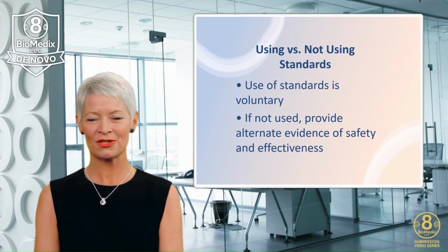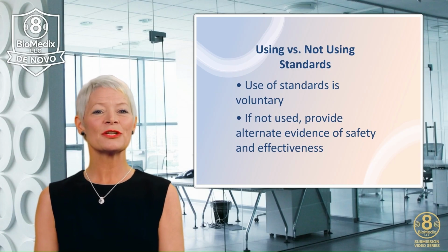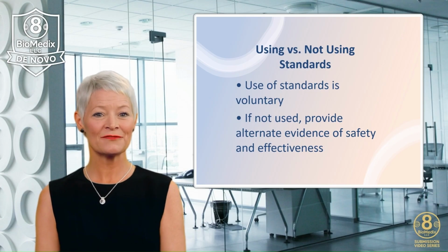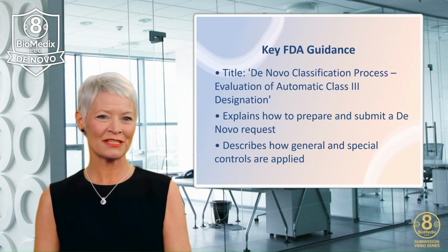However, the use of standards is voluntary. If you choose not to use a recognized standard, you must provide alternate evidence to demonstrate your device's safety and effectiveness. Always confirm you are using the FDA-recognized version of the standard. Different editions may not be accepted unless a clear justification is provided.